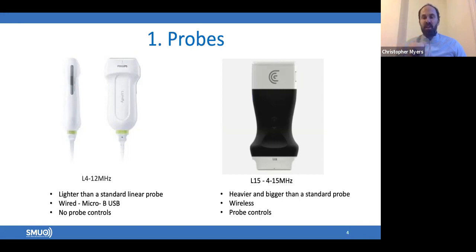There are no probe controls, which I did see as a little bit of a negative. Hopefully their second version will have that, because obviously you are using a touch screen, and sometimes if you get quite a lot of gel on your hands, then using the tablet can be a little bit difficult. So having the ability to freeze or save a cine loop from the probe itself can be an advantage, which leads us on to the Clarius version 2, which does have probe controls. You can just about see the probe controls here.